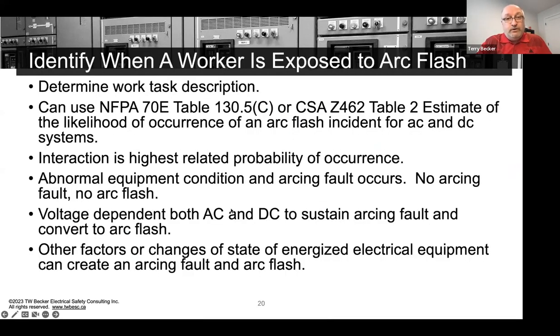All right. So when is a worker exposed to arc flash? Same comment, work task. So what's their work task? We need the work task description first, and then that'll determine if the worker's interacting in a manner that they could create an abnormal arcing fault with their interaction. Now 70E and Z462 provide us with task tables in the last two editions, and in their work task tables, there's about 31 work tasks, generic, low and high voltage, AC and DC. So not all work tasks would apply to an employer and their employees or workplace, but it starts with the work task, reference those task tables, interaction, highest related probability of occurrence.